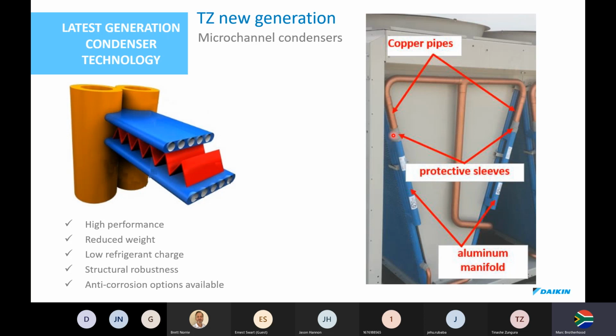So what we do is we galvanically isolate the copper from the aluminium with these protective sleeves. Because initially, this is going to be where the leaks are going to happen on this connection. Where the copper touches the aluminium under these gray bits, it's going to form a battery. So we've already got protective sleeves in place to prevent the galvanic corrosion taking place.